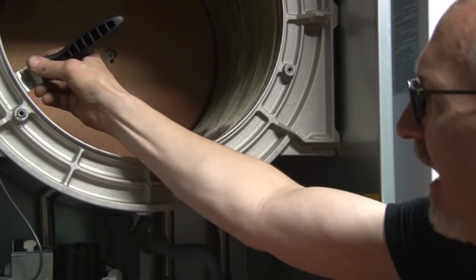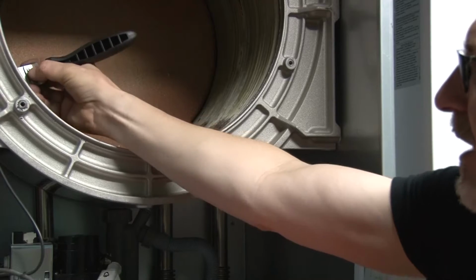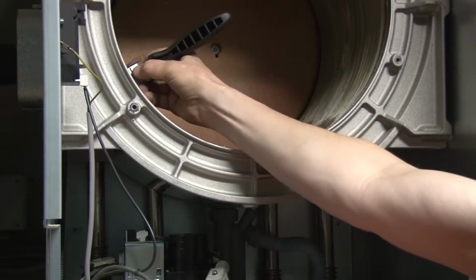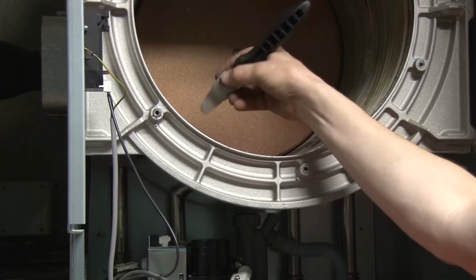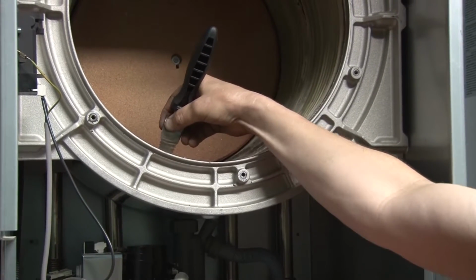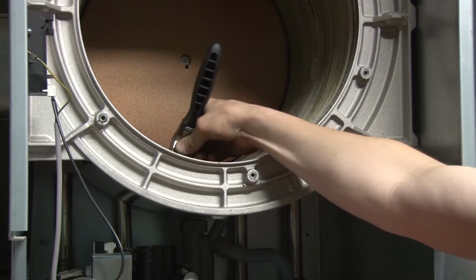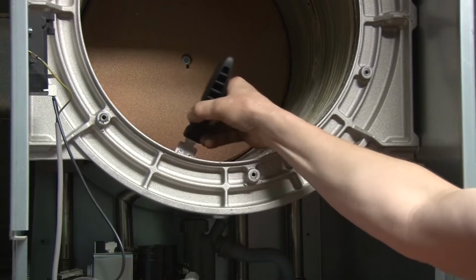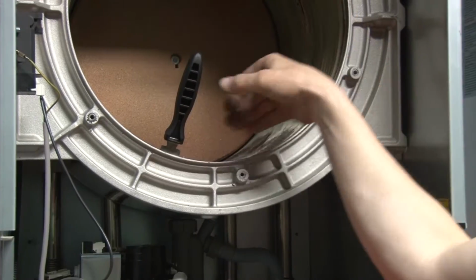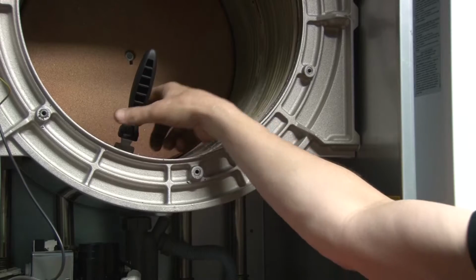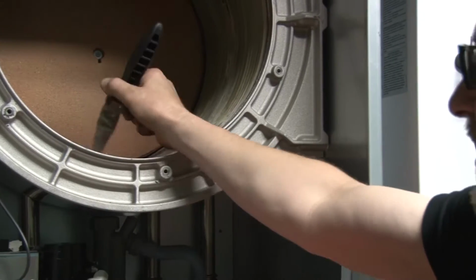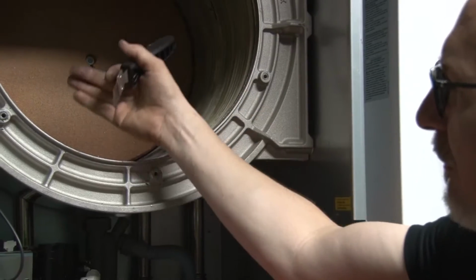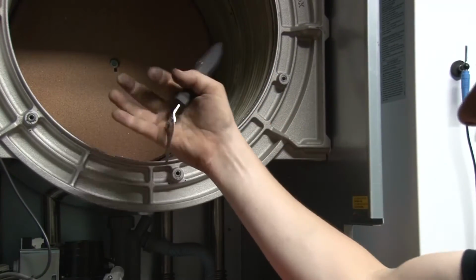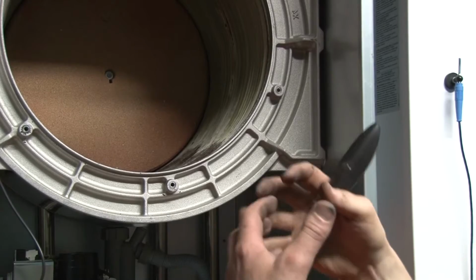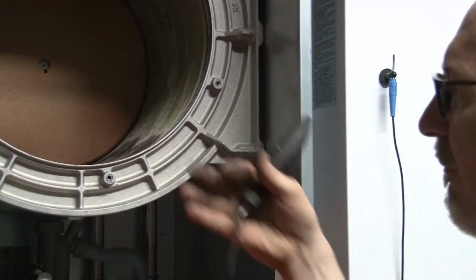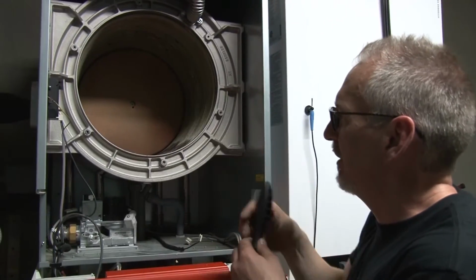But I can't take this little knife and move it more than the space it can fit into. Those dimples are going to be on either side of it. So it's not for scraping; it's to get in there and punch down through these coils to make sure that flue gas passageway is open. My whole goal here is to go front to back, all the way back, through all those gaps, to make sure the heat exchanger is good and clean. That means all those flue gas passageways are open, 360 degrees around, for nice even heat transfer. Every area of that coil is going to get a similar temperature from the flame, so we're not building up little hot spots in the boiler.